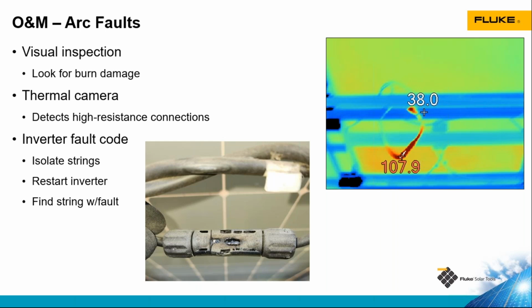There's a troubleshooting workflow you can use with inverters to find the general location of an arc fault. You shut the inverter off, isolate a section of the array, and then turn the inverter back on. If the arc fault is in that section of the array, the arc fault indicator on the inverter will go away. Then you know that's the part of the array that's got the problem. If the arc fault warning remains, then you know it's not in that section of the system. Then you shut the inverter off again, reconnect that section of the array and disconnect a different section of the array. And you keep going through that troubleshooting process until you find out where the arc fault is.